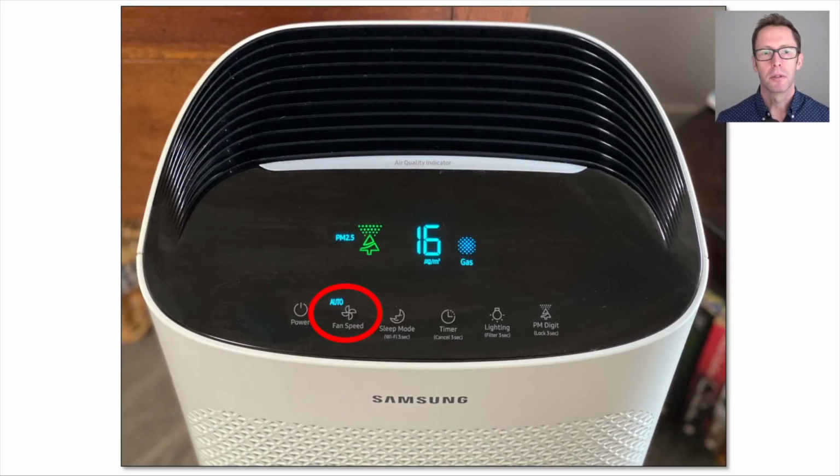A couple of other practical points on HEPA purifiers. Quite a lot of units have an auto setting. Auto in this case means that it senses smoke or other pollution in the air. HEPA filters have no way of detecting viruses in the air, and so what happens is if you use the auto setting and there is no smoke, it decides that it'll put it on a very low fan speed, and this is obviously of no benefit if you're trying to actually remove viruses from the air. So you should never use the auto setting. It should be on as high as possible a fan speed for as much of the time as you can.